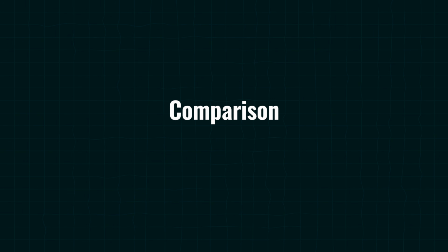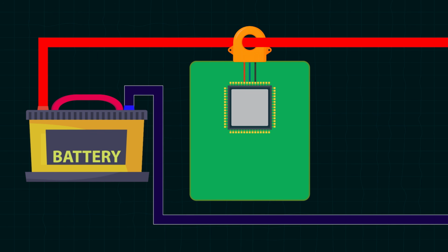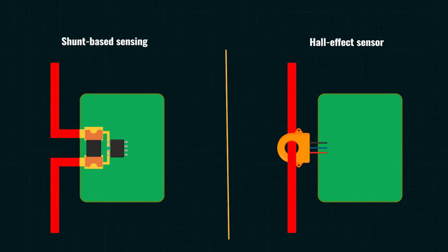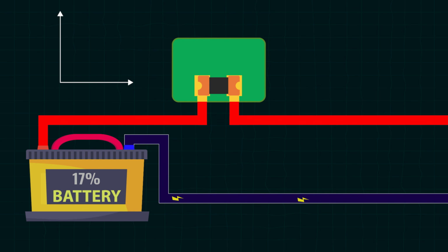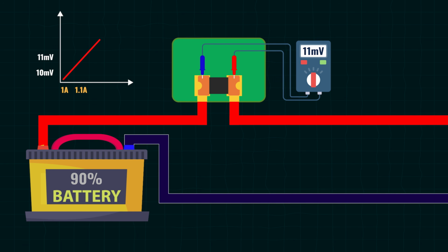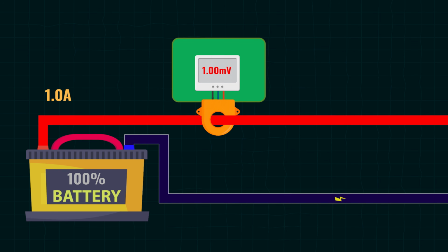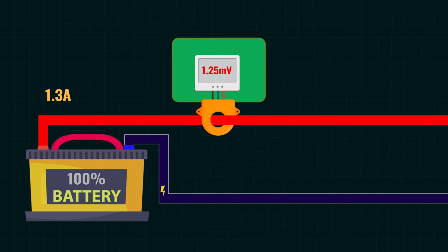Now comparing shunt and Hall sensing. Both of these approaches are widely used in battery management systems, but each comes with its own trade-offs. Let's compare them across key metrics. First is accuracy. When we talk about accuracy, the current sensing precision can make all the difference. Shunt-based sensing offers excellent accuracy, because it measures a voltage drop across a known resistor, so it gives a highly linear and precise reading. That's why it's the preferred method in applications where exact current measurement is critical, like estimating state of charge or Coulomb counting. Hall effect sensors, on the other hand, are generally less accurate, especially at lower currents. They're more sensitive to temperature changes, sensor drift, and external magnetic fields. Still, they're accurate enough to detect high current levels, short circuits, and fault conditions, or for general monitoring.